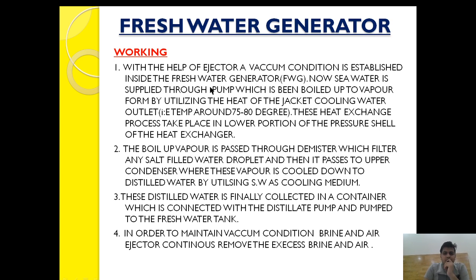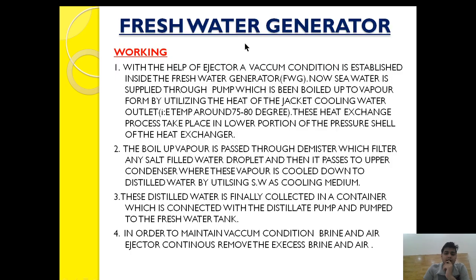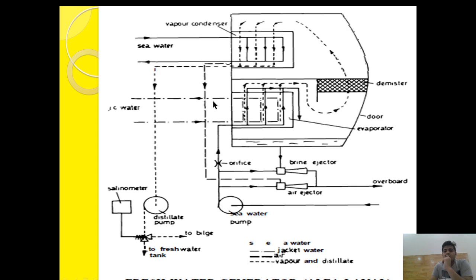With the help of the brine ejector and air ejector, a vacuum condition is established inside the fresh water generator cell chamber. Sea water is supplied through the pump and boiled up to vapor form by utilizing the heat of the jacket cooling water outlet. The sea water takes suction from the sea water pump and is passed through a restricted orifice to the evaporator, where it exchanges heat with the jacket water coming from the engine outlet at around 75 to 80 degrees Celsius.